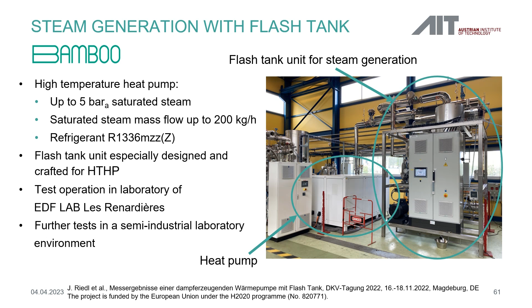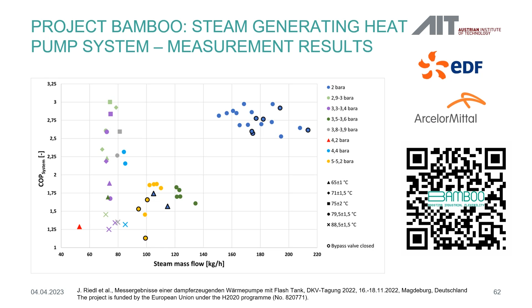With this installation, we have done many different tests also to learn about the behavior and the control parameters in this coupled system. In this diagram, you see the steam mass flow on the x-axis and the COP on the y-axis. It's again the heating COP, with the amount of heat that is delivered divided by the electricity that is consumed. The colors show the pressure of the steam that was produced, which is basically an indication of the heat supply temperature. So it is saturated steam. The blue dots represent 2 bars, which is 120 degrees C, and the yellow dots are 5 bars, which is 150 degrees C. So this was also a very successful demonstration project, and it illustrates how heat pumps that produce hot water can be retrofitted into steam generating units.